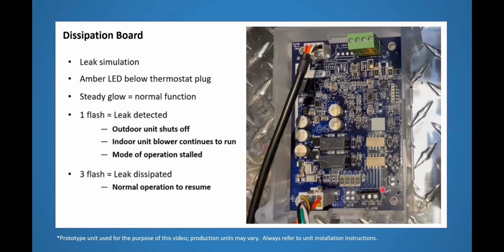And the bottom right-hand side is a miscellaneous alarm contact, which a year ago I initially thought was a waste of time, but it does have some pretty good uses. For starters, on a commercial building, you may choose to wire one of these contacts to a building automation system. If a rooftop or air handler has a leak, it can notify the BAS that there is a leak, and then the building operator can get an email, text message, screen pop up, whatever it is, saying, hey, you got a leak on rooftop 6, right? So it can do that kind of stuff. It can also turn on idiot lights on a panel or make a little buzzer beep or one of those kind of things. In other applications, residential and light commercial, we've been using this on zoning systems.